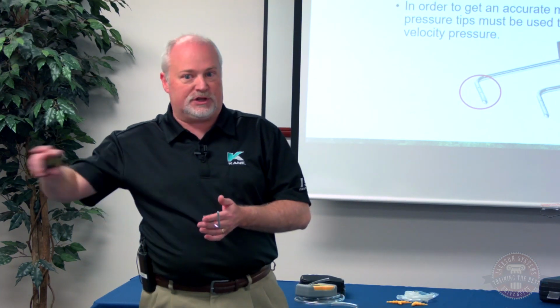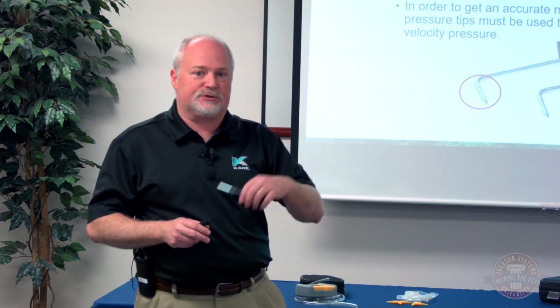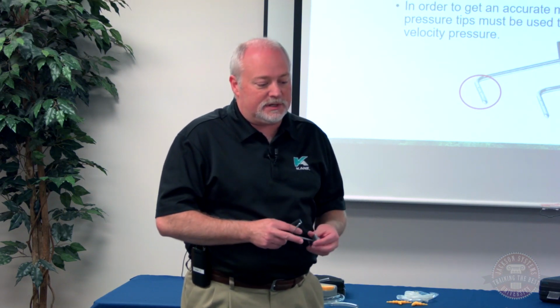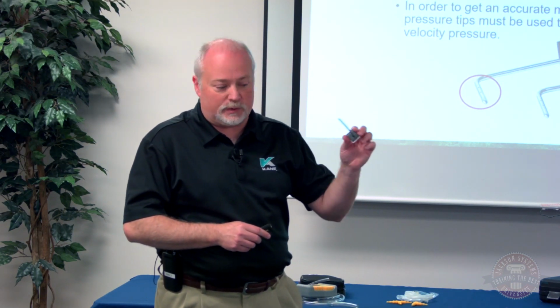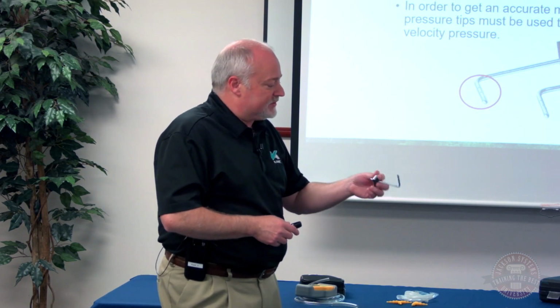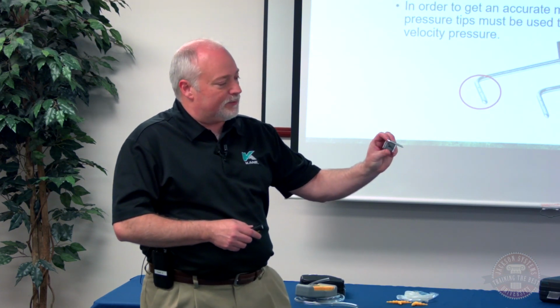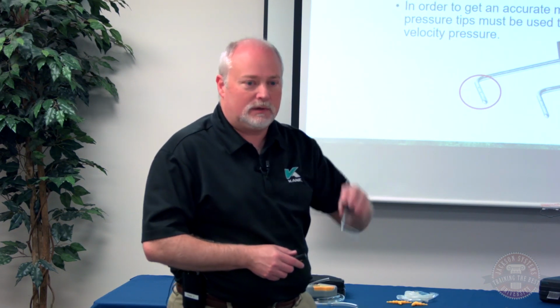That basically is telling us, when we measure external static pressure, how much pressure the fan has to work against, whether it's drawing through the return or pushing through the supply. Those two combined give us our total external static pressure. Typically that's measured in inches of water column. And we use these static pressure tips. One other thing to point out too, they've got a magnet on the back of them. So when we drill that small hole in our duct, we can put that up and it's going to stay in place with that magnet.